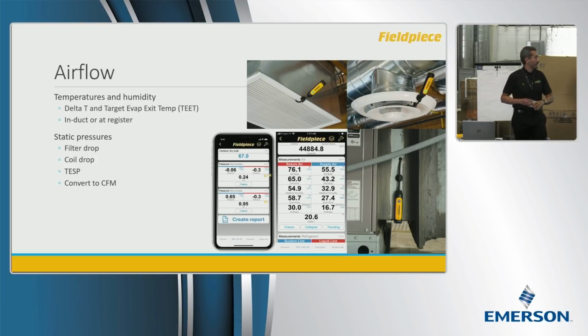And we can perform a couple different tests here. We can do a delta T test, and we can do a target evaporator exit temperature test at the same time. We have to determine the best location to take the measurements, either in duct or at a register. Now, typically in the real world, what is going to determine where I take these measurements? What do you guys typically? Accessibility, right? Ideally, it would be great to get in duct every single time because that would be a more accurate measurement. But many times, it's just not accessible or it's a real pain in the butt, and maybe it's just not worth it. So we might decide to hook up at a grill or at a register.